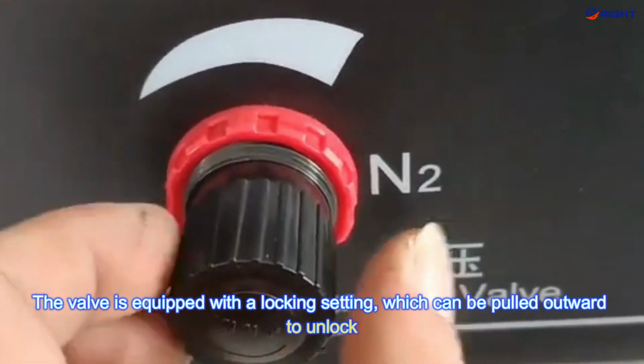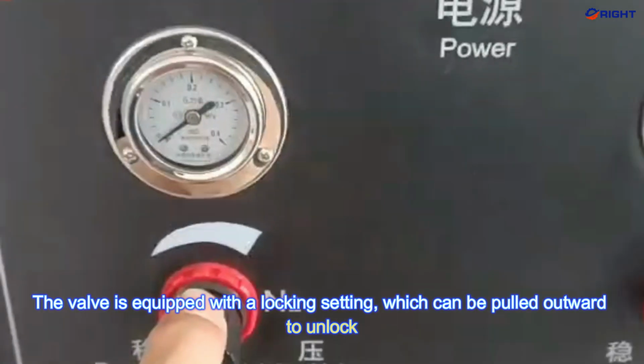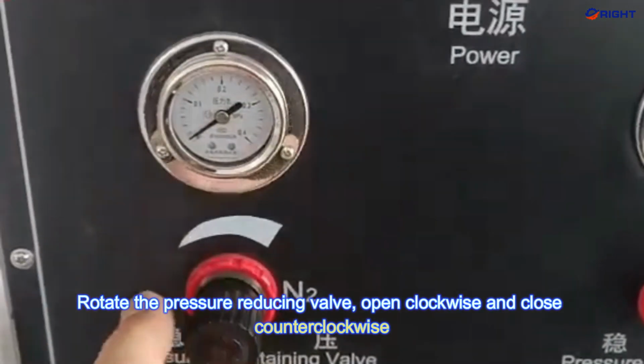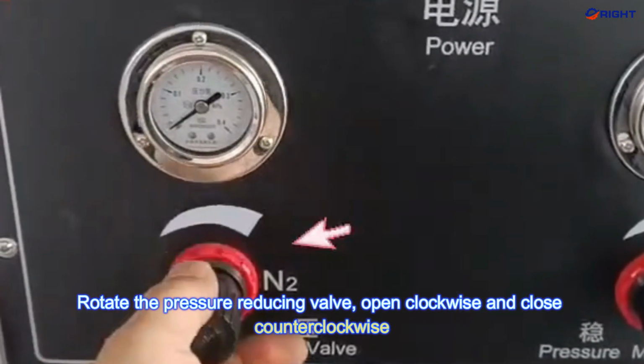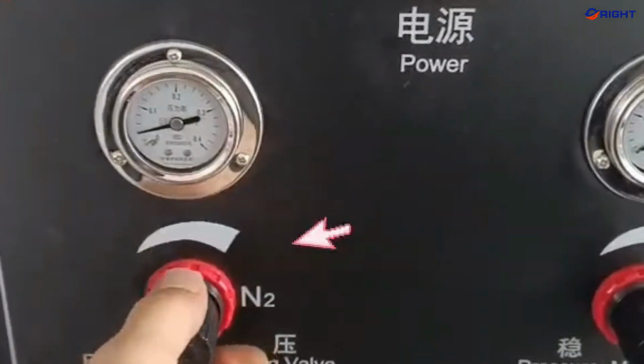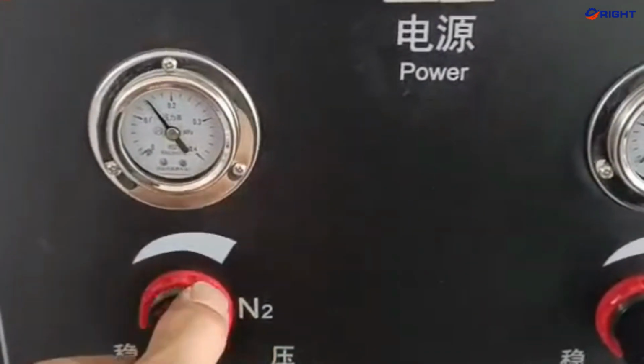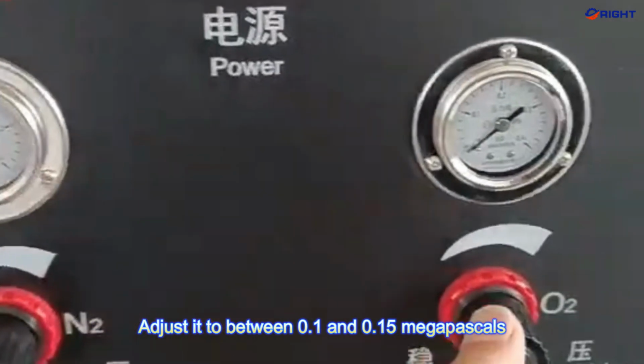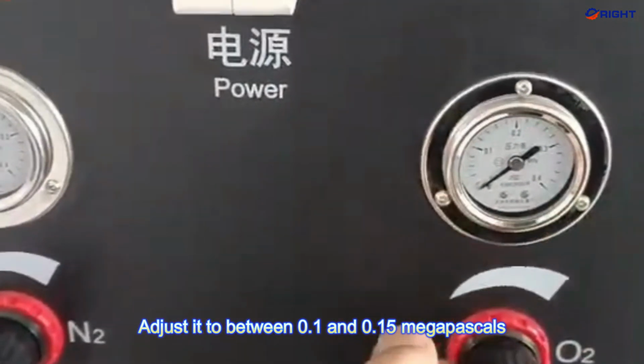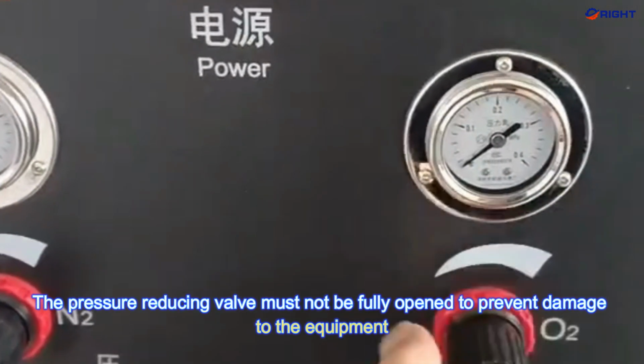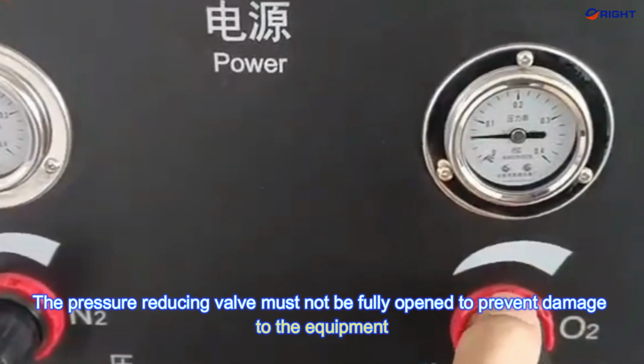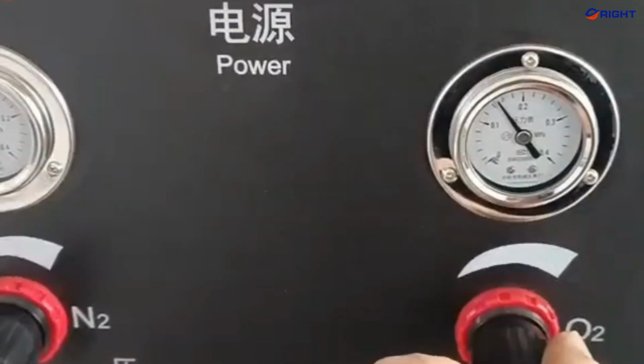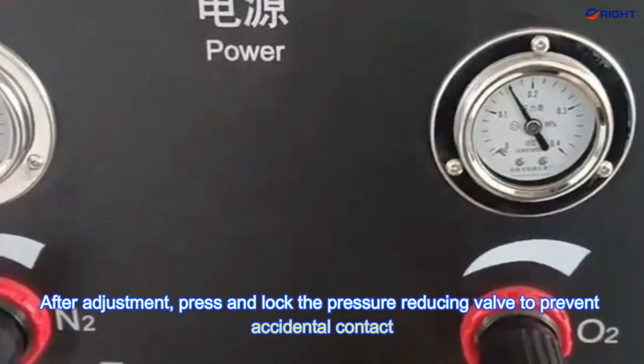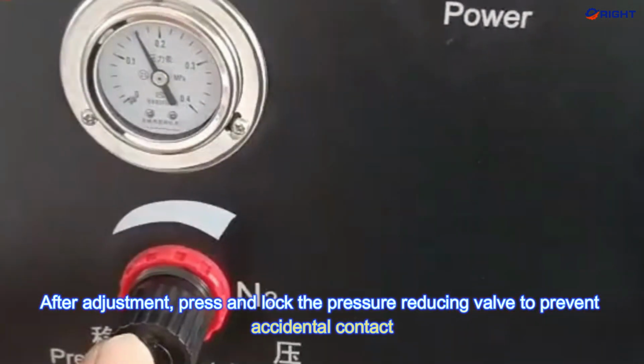Pull the valve outward. The valve is equipped with a locking setting, which can be pulled outward to unlock. Rotate the pressure reducing valve, open clockwise and close counterclockwise. Adjust it to between 0.1 and 0.15 megapascals. The pressure reducing valve must not be fully open to prevent damage to the equipment. After adjustment, press and lock the pressure reducing valve to prevent accidental contact. Click again to turn off voltage regulation.